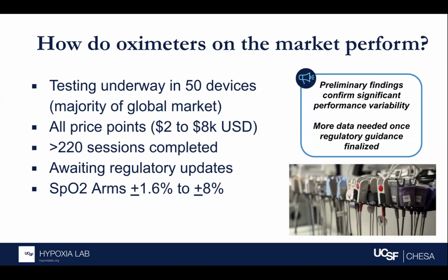We've done over 220 sessions. We are awaiting regulatory updates still for what the new standard will be. That is not out yet. We are trying to anticipate, and we continue to test and gather more data. And I'll share a little bit more about this in a slightly later session. But we've completed testing for our initial goal, which was to test 24 subjects per device. It is likely that we are going to end up needing to test 100 or more per device, just to put it into perspective, in order to power these studies.